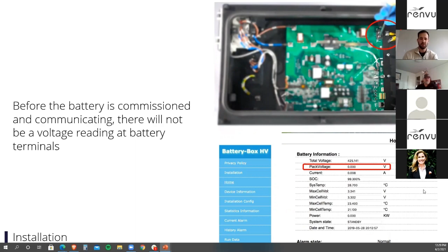One of those safety features is that it won't instantly energize those terminals. It waits until it begins communicating with the inverter. A lot of first-time installers make the mistake of stacking up the battery, turning it on, taking a voltage reading, getting 0 volts, and assuming the battery is dead. That's not the case—it just needs to be commissioned and communicating. Then a handshake occurs between the inverter and battery, and it applies the voltage. So watch out for that, because people think they've discovered a big problem when it's not. The thing to actually look out for is whether there's an alarm—give us a call if you see one, and we can help you sort it out.